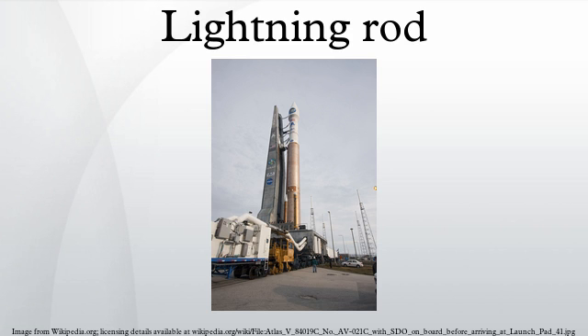It is standard practice to approximate the sphere's radius as 46 m near the ground. An object outside the critical distance is unlikely to be struck by the leader if there is a solidly grounded object within the critical distance. Locations that are considered safe from lightning can be determined by imagining a leader's potential paths as a sphere that travels from the cloud to the ground. For lightning protection, it suffices to consider all possible spheres as they touch potential strike points.